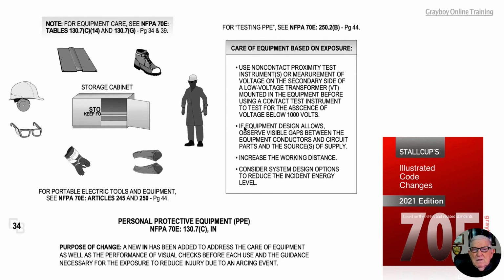The first bullet below the requirement here is if equipment design allows observed visual gaps between the equipment conductors and circuit parts and sources of energy. Make sure that the gap between terminals, say where a termination is made, has no room for tracking where a short circuit condition might develop into an electrical arc type condition. Increase the working distance. If you can stand further away from the energized component, use an insulated tool, for example, and get as far back from the part as you possibly can, naturally that would be beneficial to the maintenance worker.